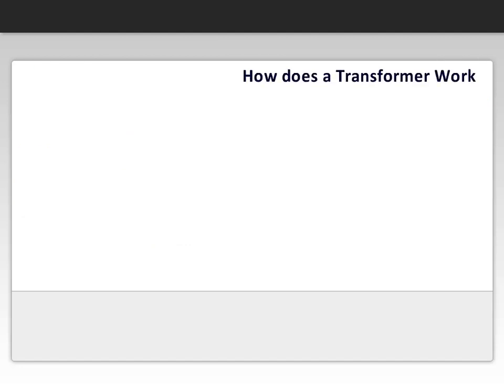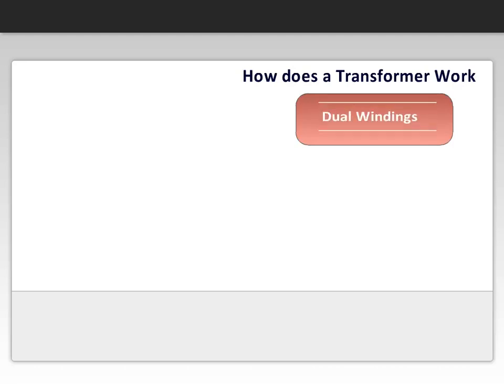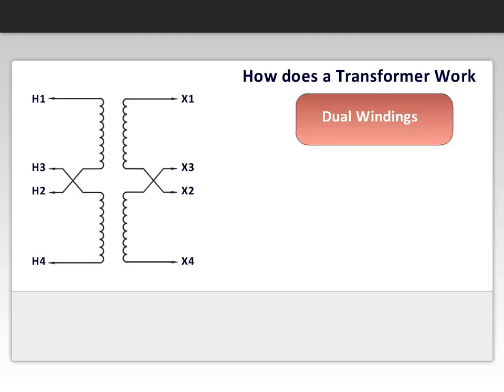Some transformers are furnished with dual windings to allow flexibility for different voltage connections in the field. Here's a typical wiring diagram for dual primary and dual secondary windings. This transformer can be connected to a source voltage of 240 or 480 volts, and the secondary can be connected to a load rated at 120 or 240 volts.